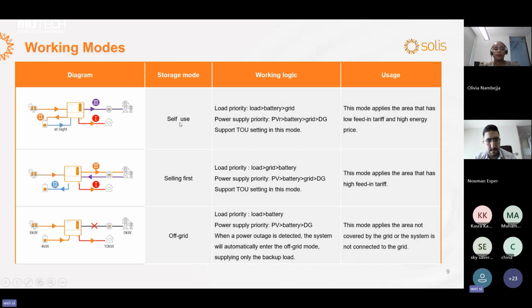In this self-use mode, we also support the time of use setting. You can set 6 time periods to decide when to discharge your battery or when to charge your battery. About the selling first mode, the priority of the load, the battery and the grid are opposite in the working logic. And the off-grid mode is very easy to understand: just charge the battery and supply power to the load.